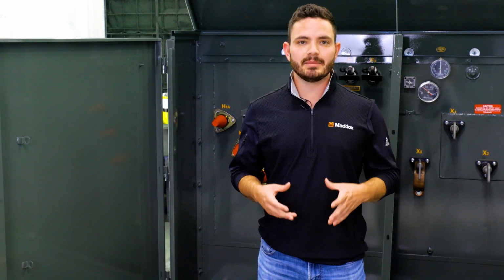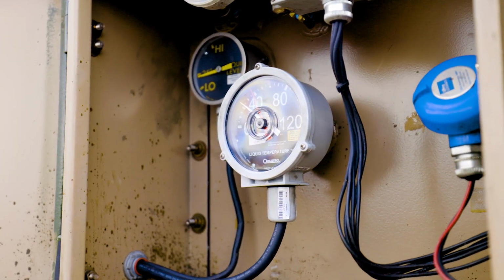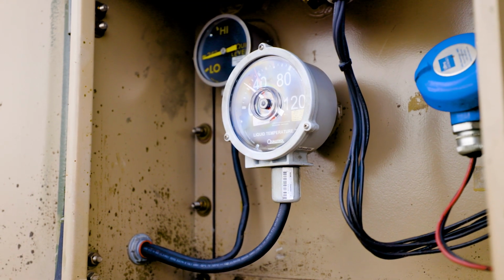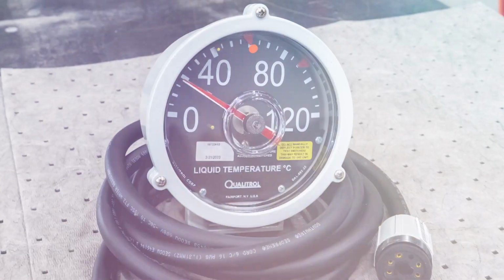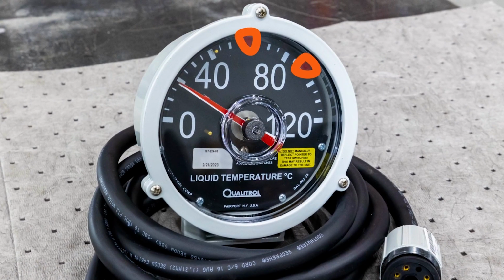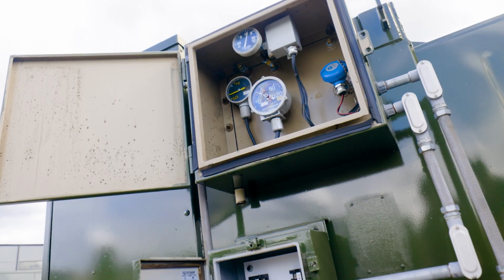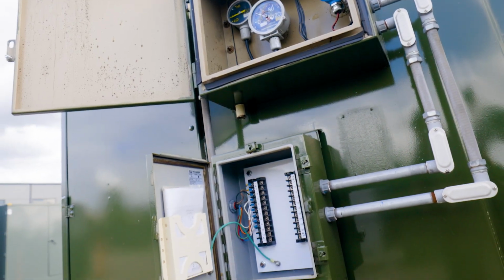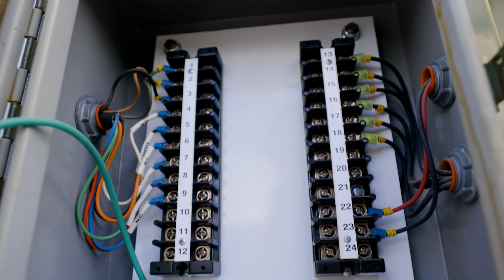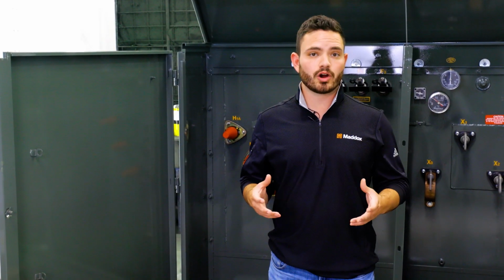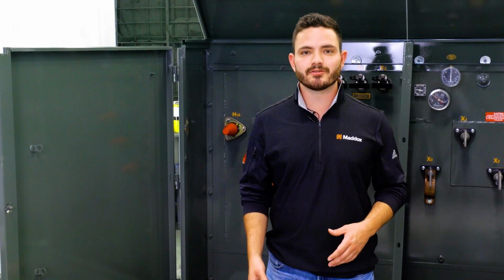Alarm contacts can be included with any liquid level, liquid temperature, or pressure vacuum gauge. They have contact points set at particular levels on the gauge faceplate. When the pointer of the gauge reaches the set contact point, the alarm contact opens or closes the circuit like a switch. If the transformer level, temperature, or pressure exceeds a certain threshold, the contacts will trigger an alarm that alerts the transformer's owner of a potential problem.